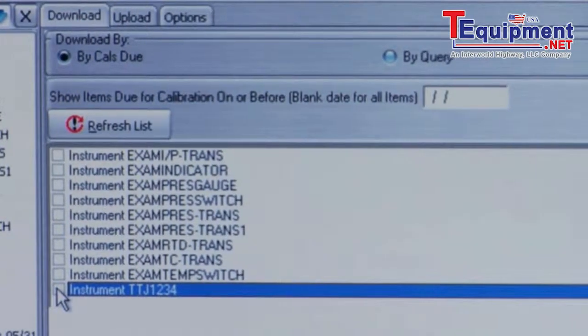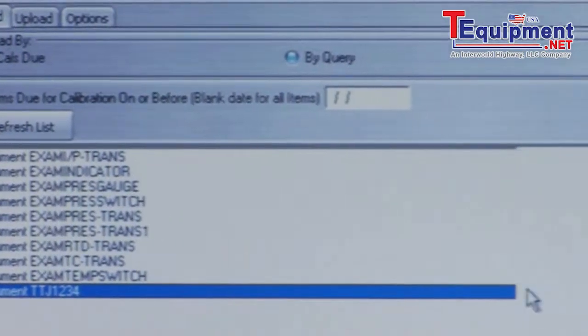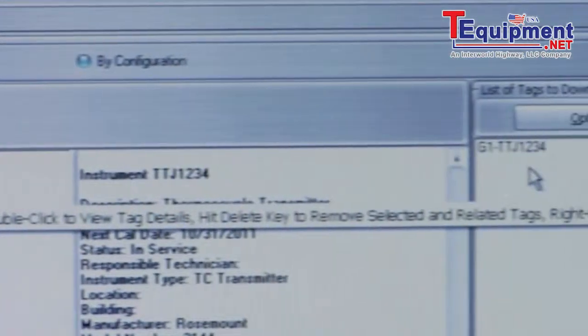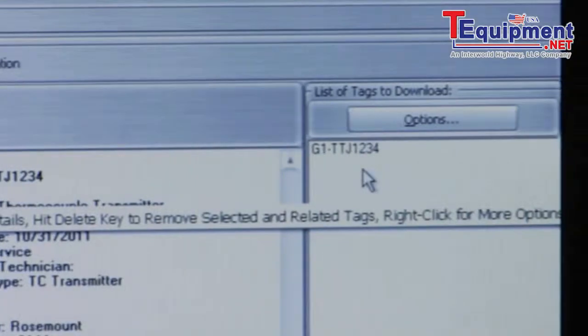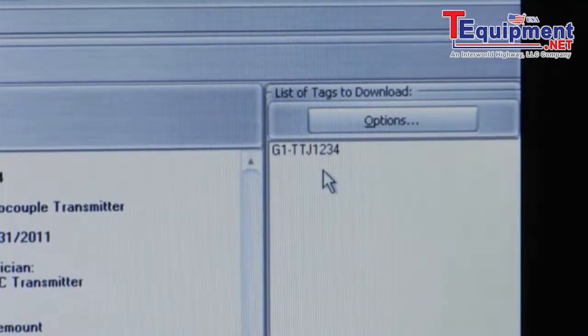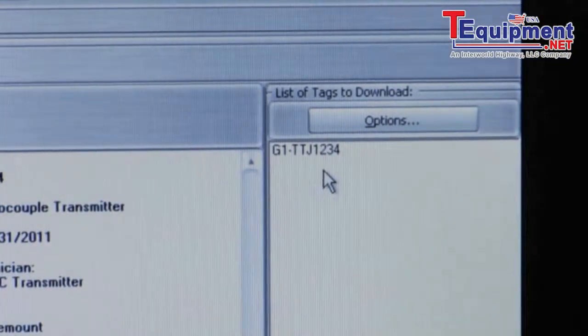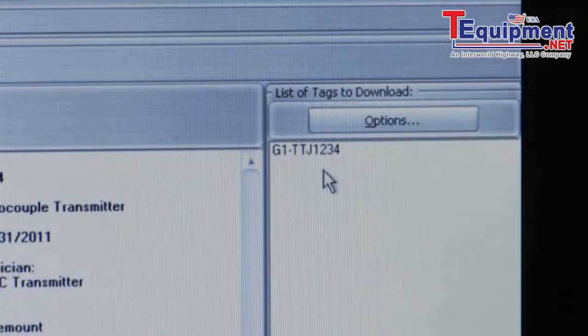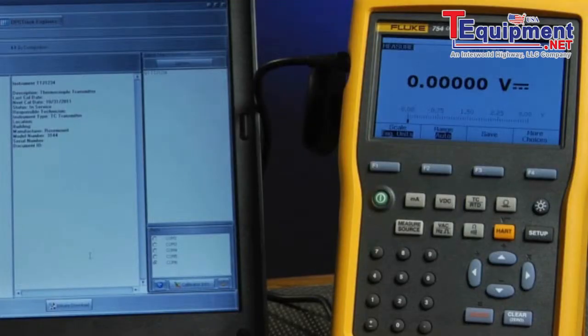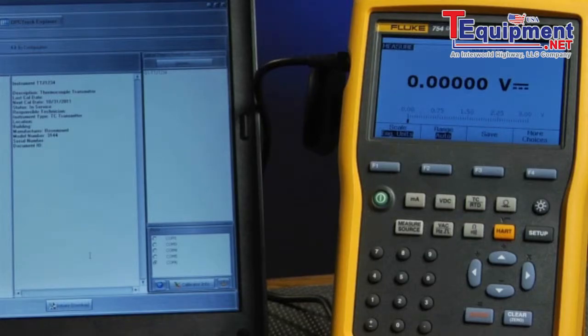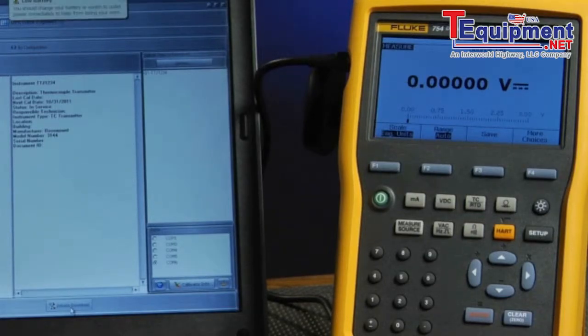By selecting a tag, it's loaded into the tags to download box. This tag is now ready for download to the Fluke 754 calibrator. We've made the USB connection between the calibrator and the laptop. Now we're going to initiate the download of the procedure into the calibrator.